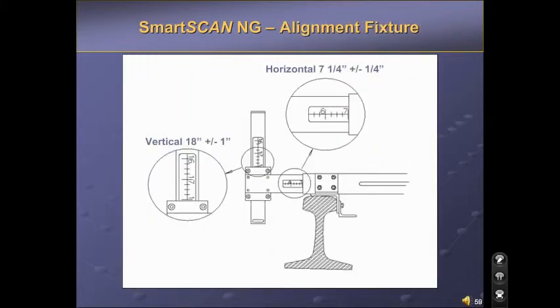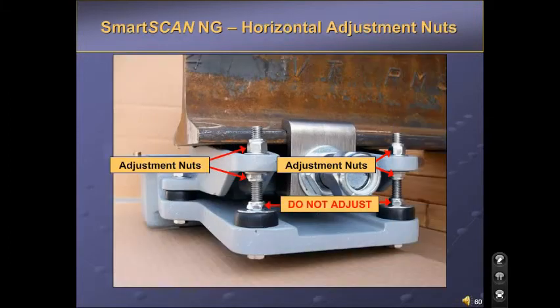The alignment fixture has ruler scales on both the vertical and horizontal bars. The correct placement of the scanner is vertical, 18 inches plus or minus 1 inch, horizontal, 7 1/4 inches plus or minus 1/4 inch. When making a horizontal adjustment, be sure that the nuts are moving equally on each bolt to keep the scanner mount parallel to the rail.